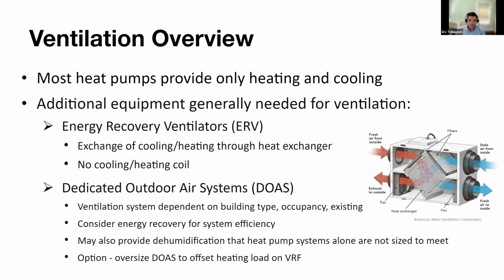So most heat pump systems are only going to provide heating and cooling to the space. So you might need additional equipment for ventilation. Two main kinds are ERVs and dedicated outdoor air systems. So ERVs are just an exchange of cooling and heating through a heat exchanger. There's no additional cooling or heating coil. Basically, there's two fans. There's an exhaust fan that's taking the air from inside your space and exhausting it out to the atmosphere. And then there's a supply fan, which is pulling outdoor air and then serving that into your space or inside your building.